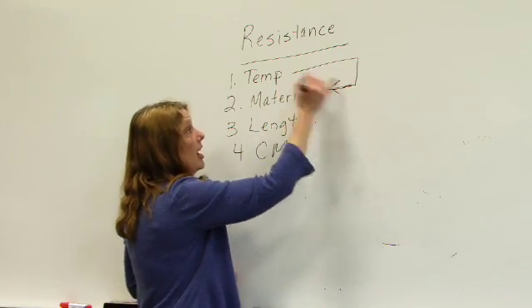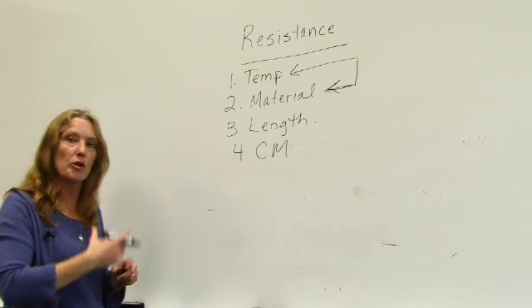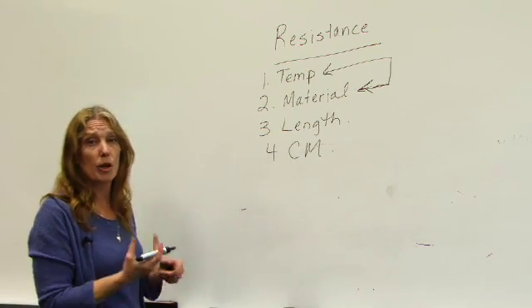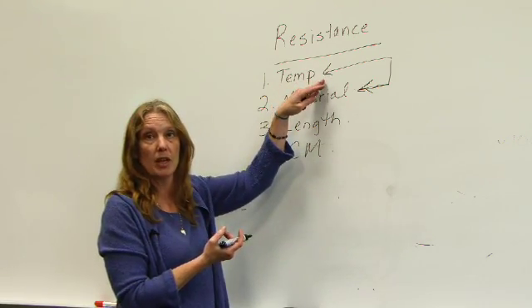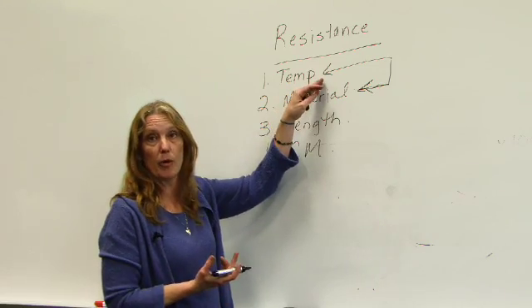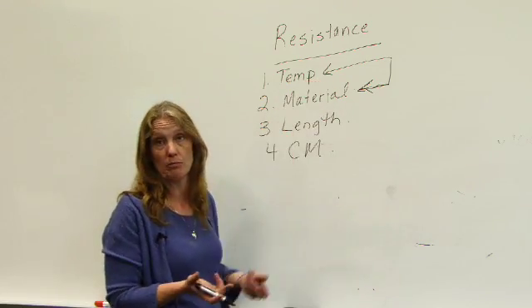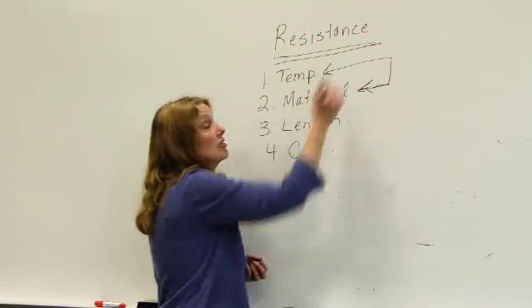And temperature. Obviously, when we increase temperature, resistance increases. So if we're using it in a warmer area or a warmer part of the country, we're going to use probably a larger size wire to account for the amount of heat. If we put our wire in a boiler room, it's going to be a whole lot different than putting that wire in a classroom. So that does have a determinant on how much resistance we get.